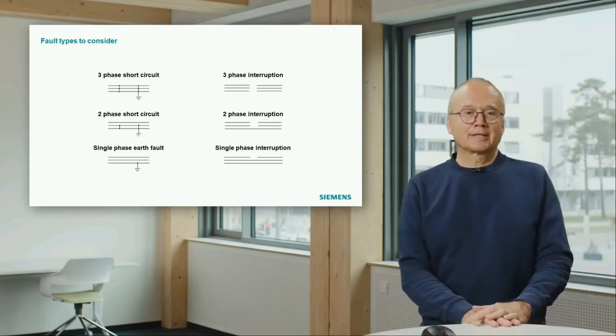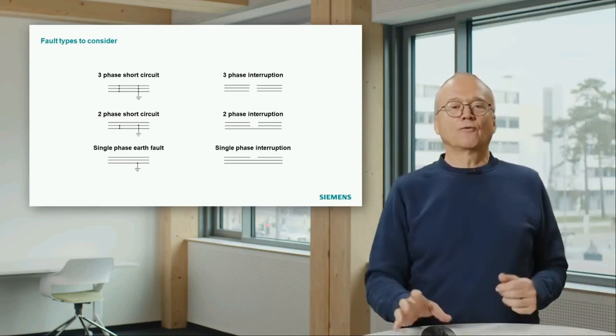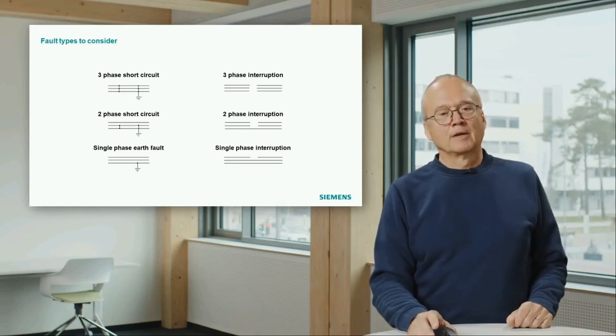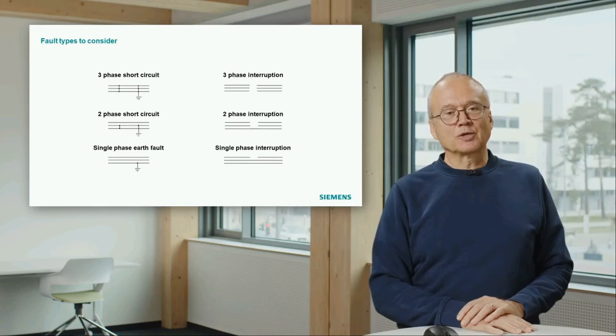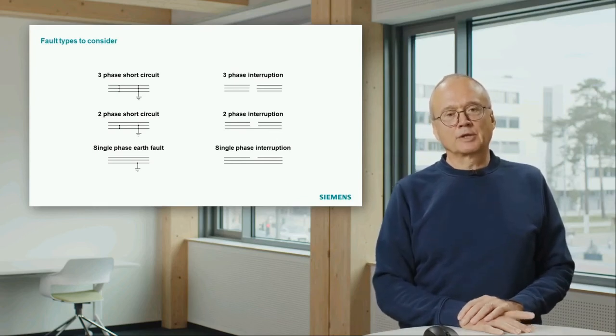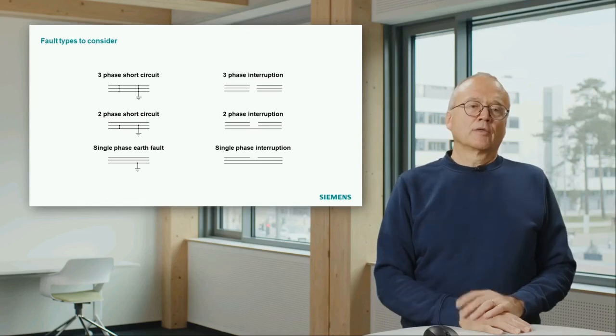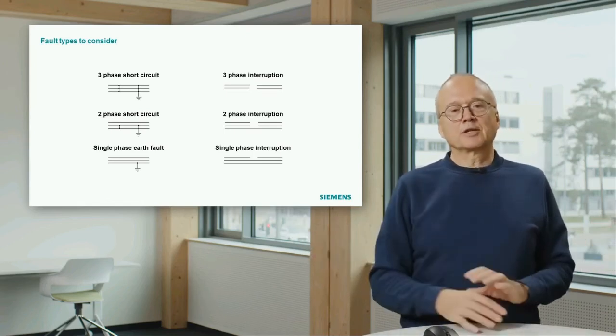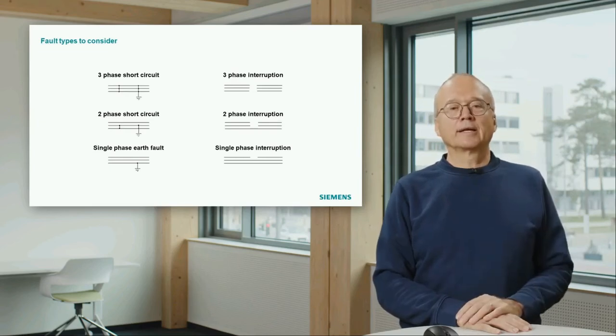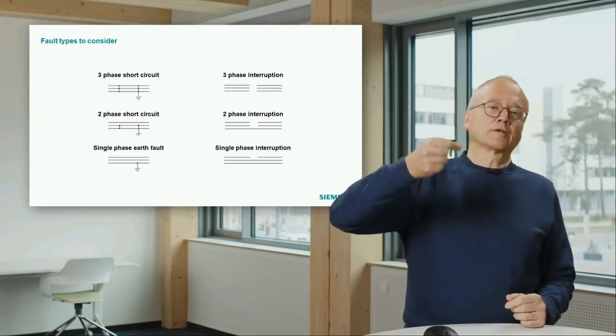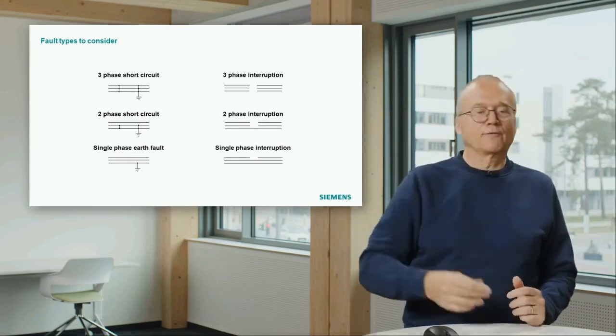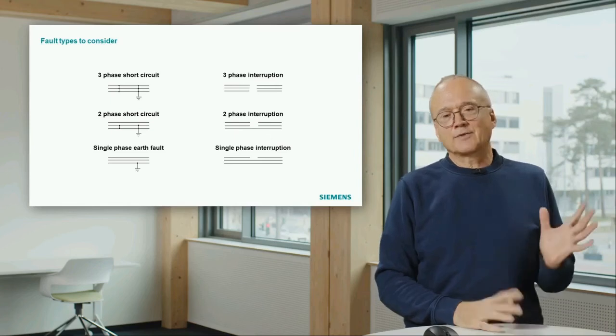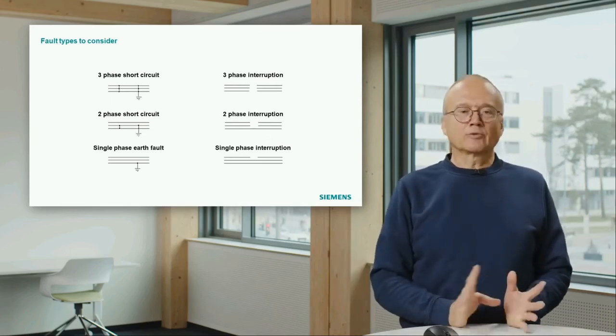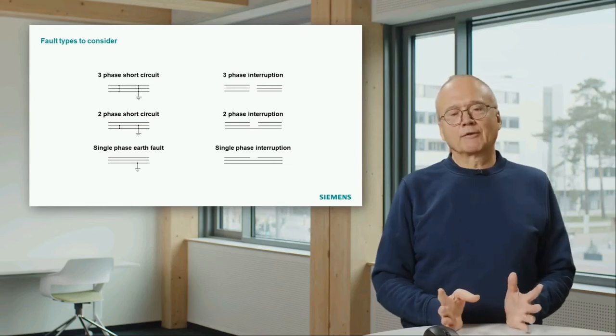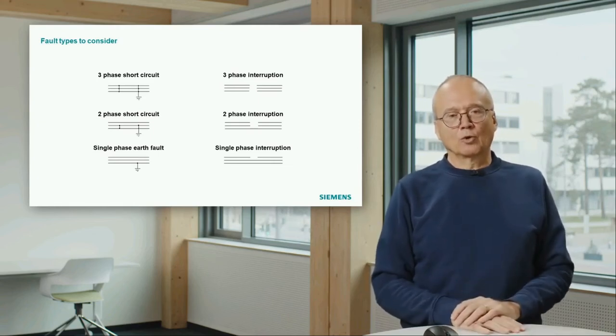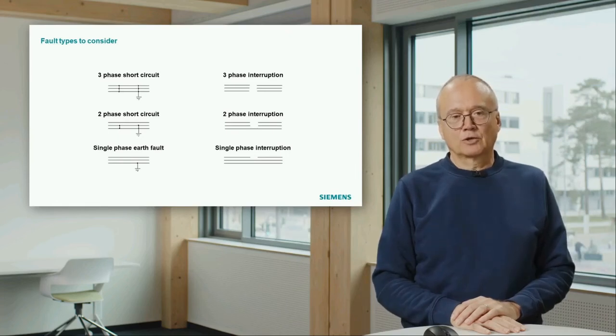And the last thing I'd like to mention here is, what types of fault do we have to consider? On the left-hand side, on the bottom, you see the most frequent type of fault, single phase to ground fault. This will occur typically, for instance, if a lightning arc hits an overhead line, you have an overvoltage there, you get a flashover on a tower, and then you have a phase to ground fault. And you can assume that in an overhead line system, roughly 80 to 90% of all short circuits are single phase to ground short circuits.